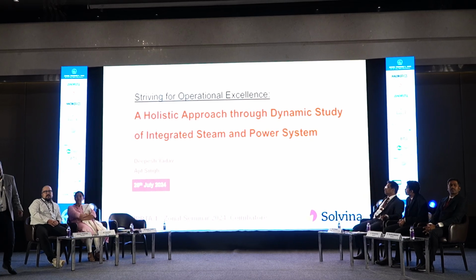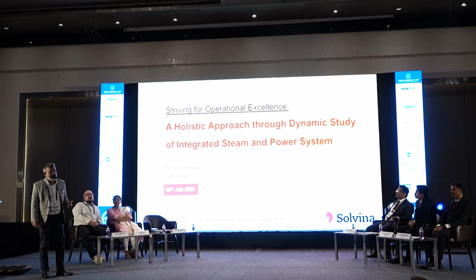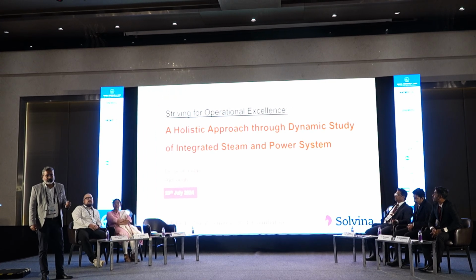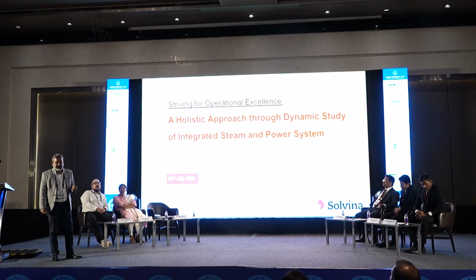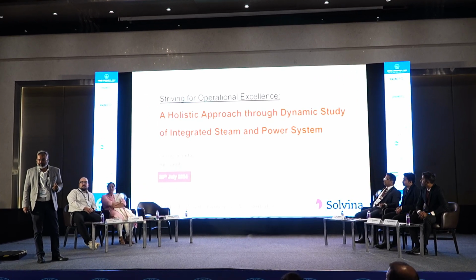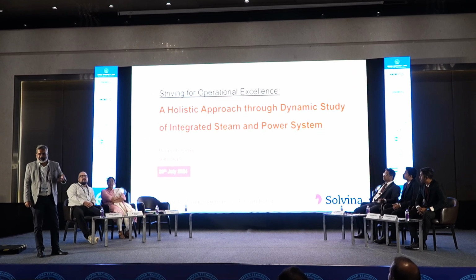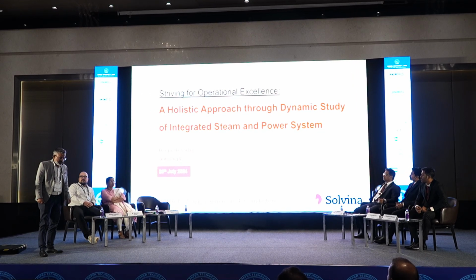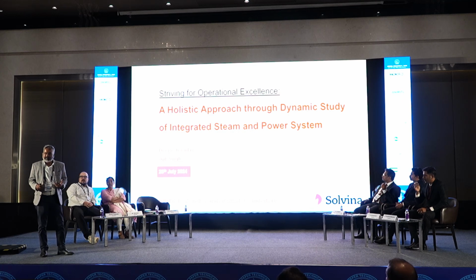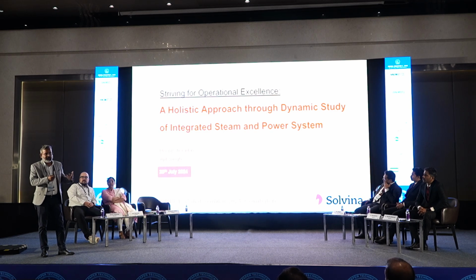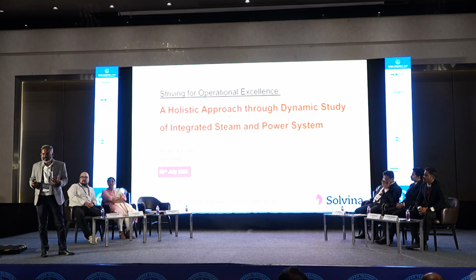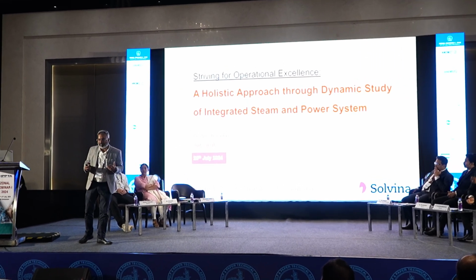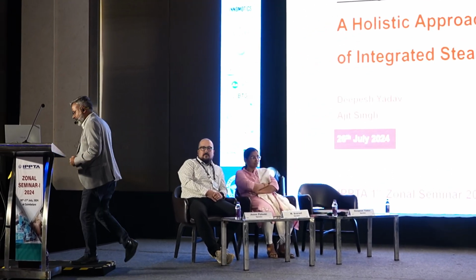Just to give you one instance, when we talk about reliability, if you recall, on July 30 and 31st, 2012, there was a severe northern grid failure. The whole grid collapsed and you can imagine the losses that we faced. Most of the islanding schemes and load shedding schemes are prepared on paper through some simulations or through some history of the data, but they are never validated. How do you validate that? How do you make sure that it will work when the plant faces the real situation? These are some of the challenges that we mostly address. So without ado, let's go through.